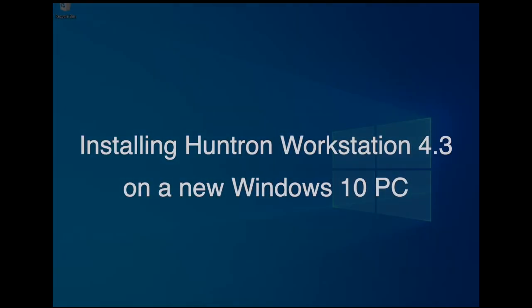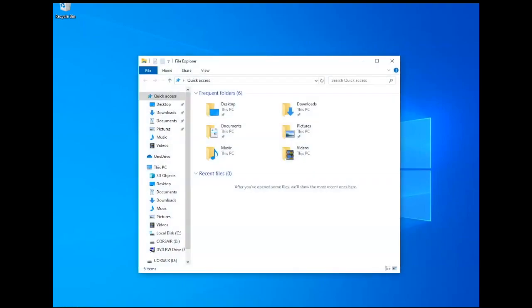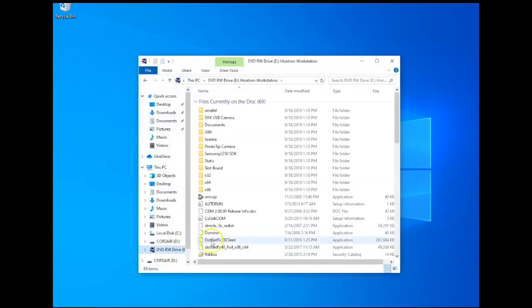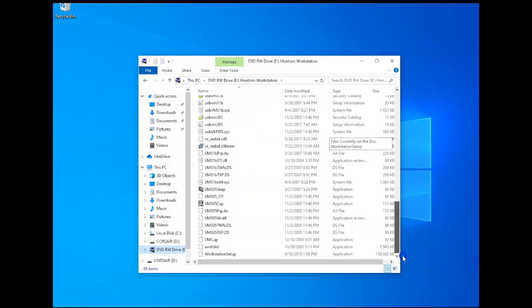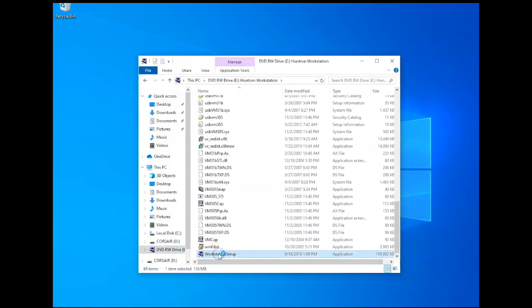This video covers how to install Huntron Workstation 4.3 on a new Windows 10 computer. To start, install your installation DVD into your computer and select it. Browse this DVD and select workstationsetup.exe. This will begin the installation process.